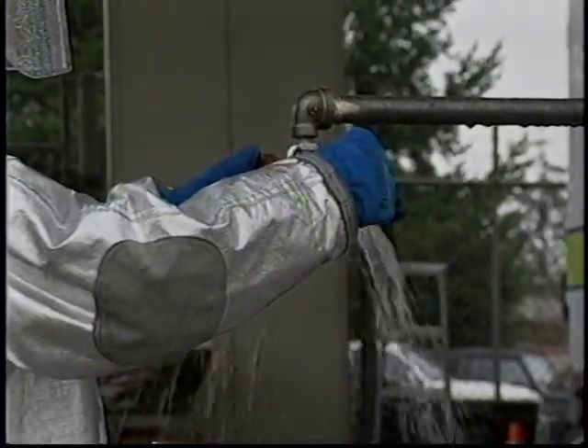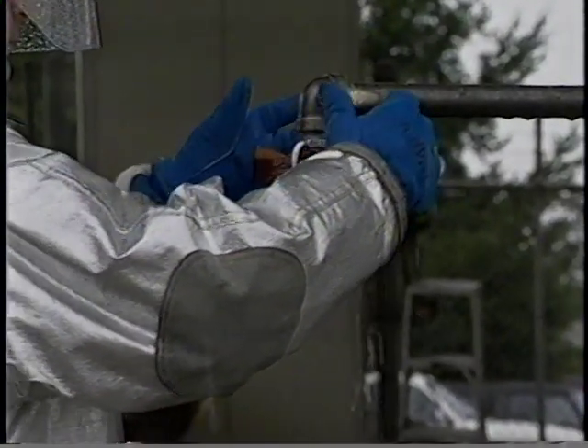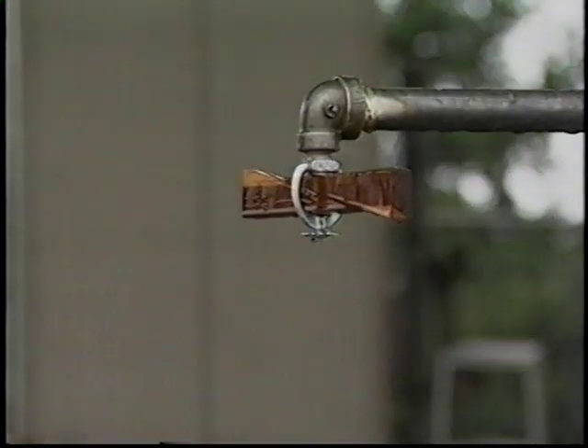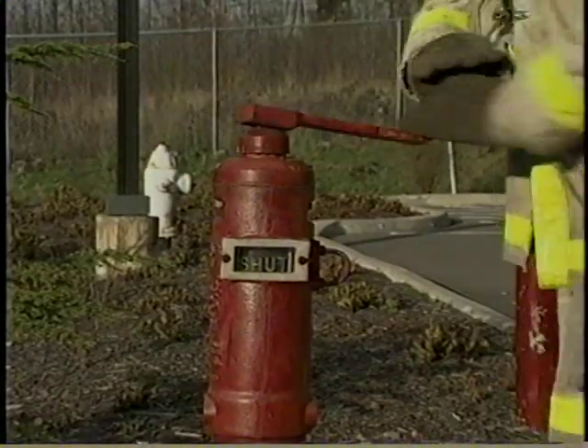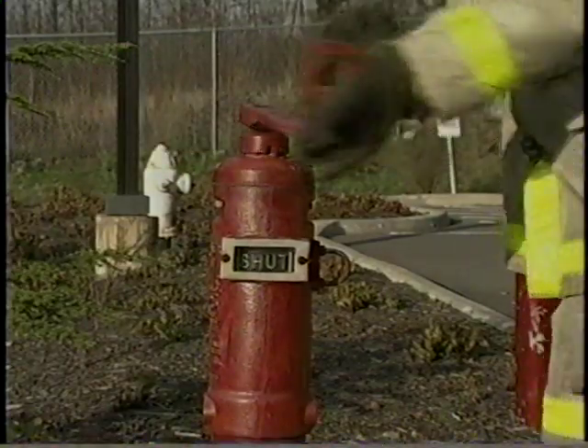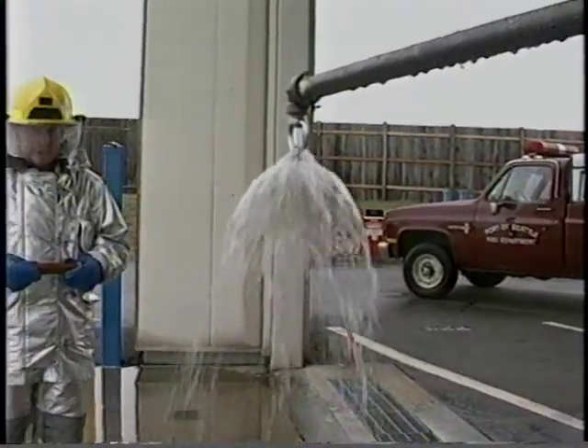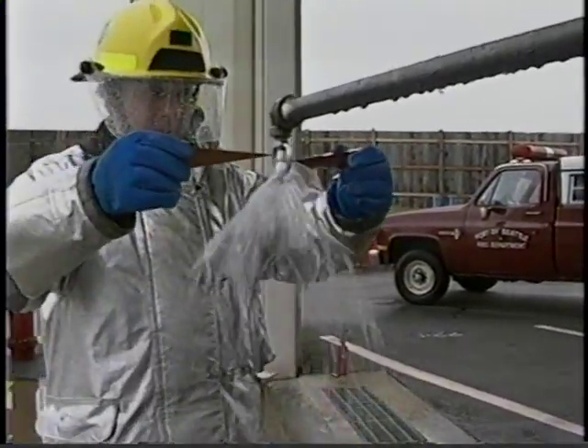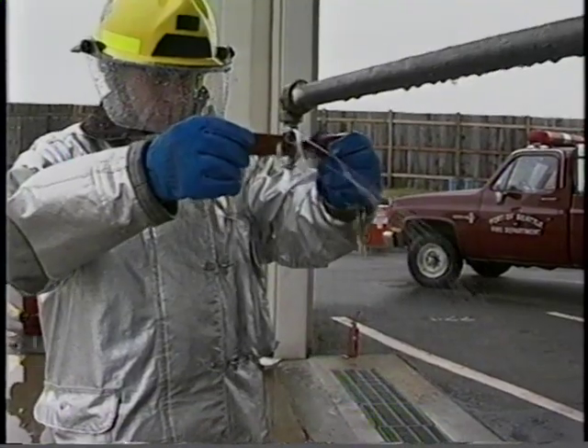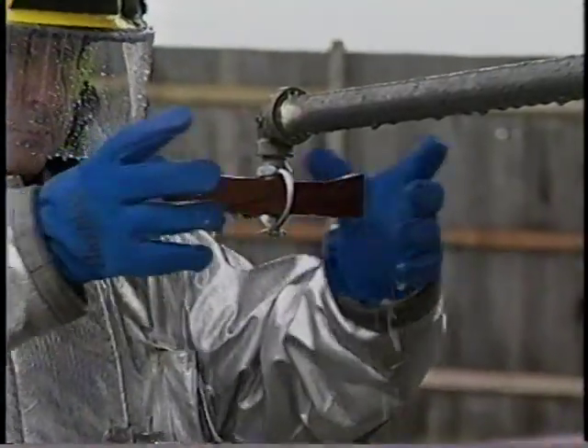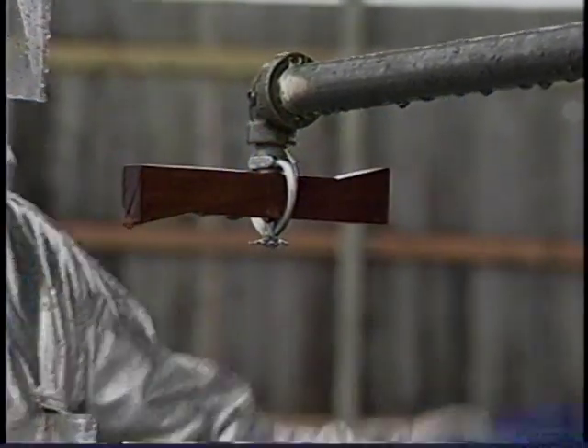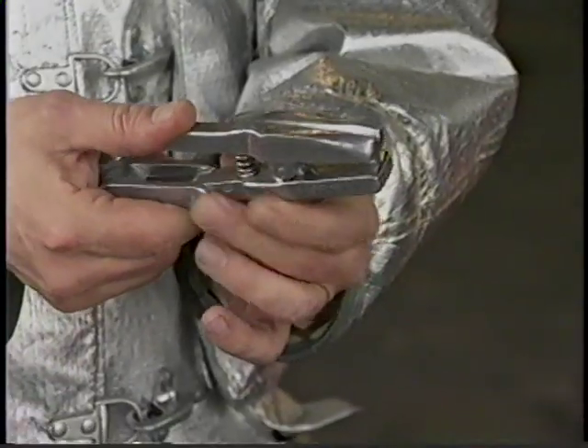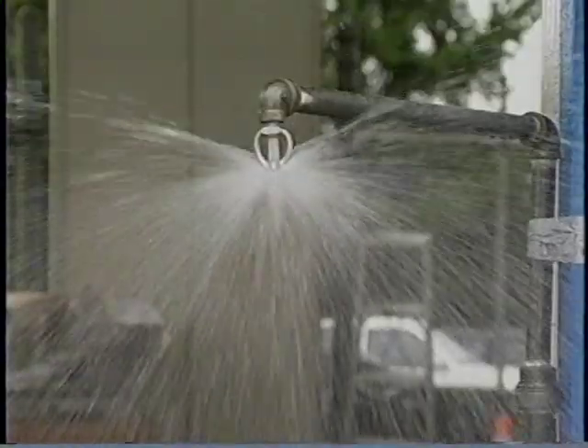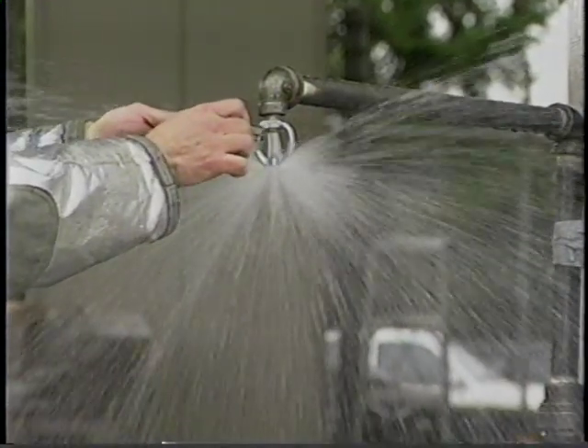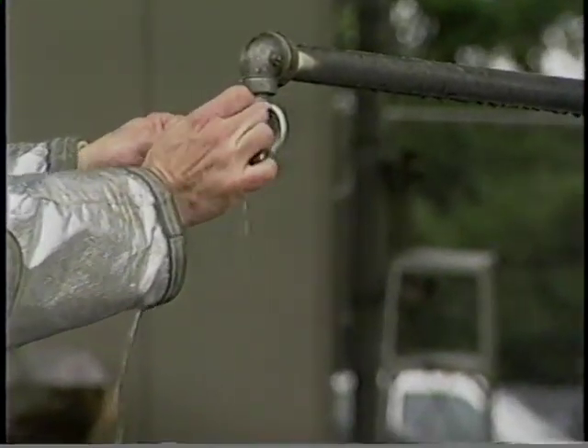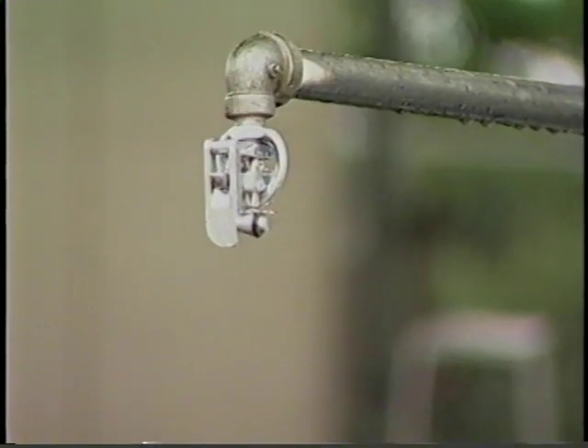Occasionally, you may need to stop the flow of water from a single sprinkler that has been activated. This may be necessary even after the main water control valve has been closed, because the residual water in the system will continue to drain through the open sprinkler. To stop the flow of water, insert small wooden wedges between the discharge opening and the deflector. Tap them together by hand until the flow is stopped. Commercially made stoppers are also available that can be inserted to plug the opening. Closing a sprinkler while water is flowing takes some practice, and all firefighters should learn to be proficient in this skill.